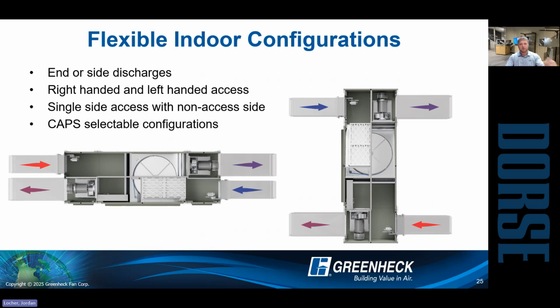The other big design point, we try to make it as flexible as possible. We do have flexible connections, so it's available in either end or side discharge. You can see those two pictures here. It just gives you a little bit more flexibility of where you want to locate those ducts and how you want to get it into the building. And then we also saw a need for a right-handed or left-handed access. I'll show you a picture here in a minute, but basically the entire back wall of that unit can be pushed up against a wall, and the entire unit can be serviced from one single side. All the filters, all the blowers, everything can come through that unit, and then offering which side you'd like that access on. A mirrored configuration is also very powerful to get it onto that job.